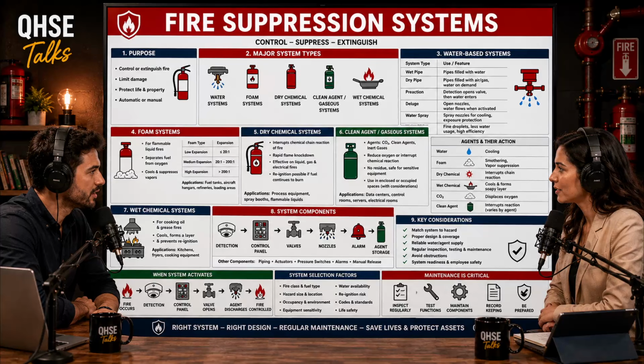Yes. The system has effectively just converted itself into a wet pipe system. But, and this is crucial, no water is flowing out of the sprinkler heads yet. Because the physical sprinkler heads are still intact. Correct. Step 2. The fire must continue to grow, generate enough heat to reach the set temperature, and physically melt the glass bulb on the specific sprinkler head. Only then does the water actually discharge.